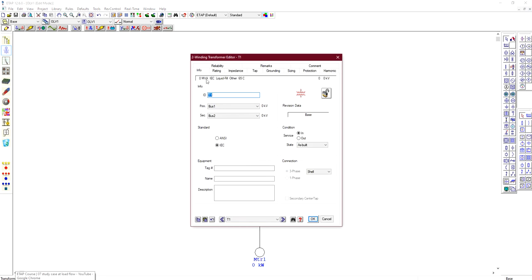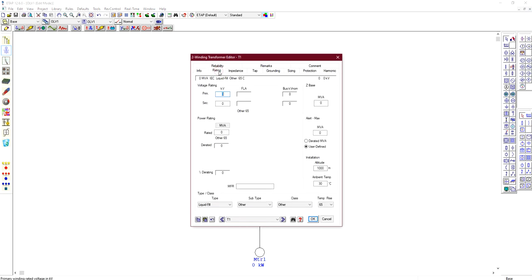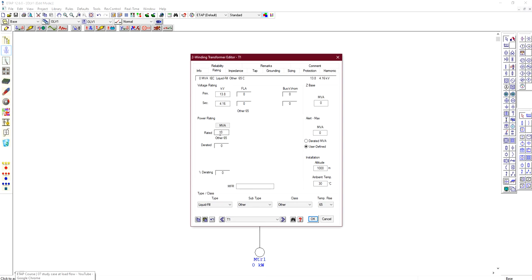Go to the rating section of the transformer. You will set the primary voltage and secondary voltage — not the turns ratio directly. The primary voltage is 13.8 kV and the secondary voltage is 4.16 kV, making this a step-down transformer. The voltage of 4.16 kV will be supplied to the induction machine. The power rating is assumed to be 10 MVA.